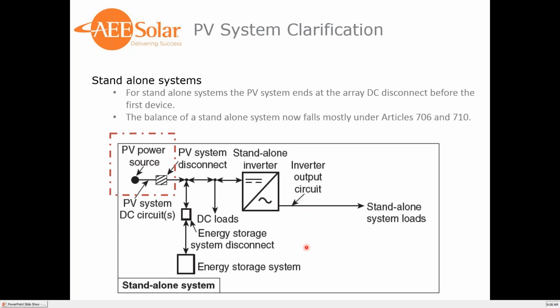Standalone system. For a standalone system, the PV system ends at the array disconnect before the first device. The balance of the standalone system now falls under Articles 706 and 710. So this is very similar to the DC coupled system that we've seen previously, except for being standalone, not necessarily operational with any other or grid connected.